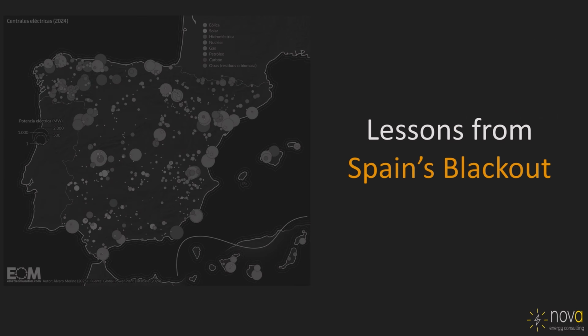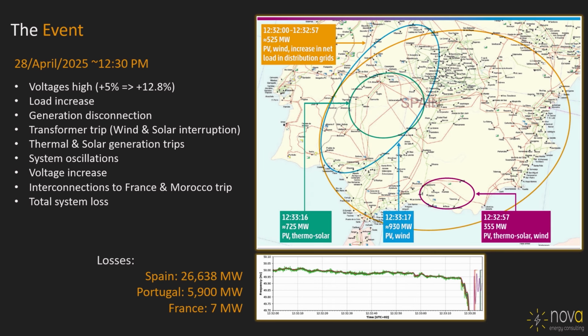So with that in mind, what happened in Spain then? It happened on the 28th of April, pretty much at noon. Before the incident started, the voltages were a little bit high on the network already. Like Fraser mentioned, there are contingencies in terms of a kind of power called reactive power that has to be ready to dispatch to compensate for those voltages and bring everything back into control.